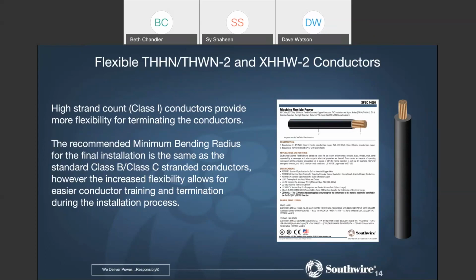However, what this is going to do for you is when you are terminating the product and you need to train or pre-bend these conductors, and you have limited room in the panels or the gear that you're installing this at, you need this extra flexibility so you can get the product installed. Then this is going to provide that for you. So it's a handy product. We're seeing a lot of people utilize it for that specific requirement. Next.